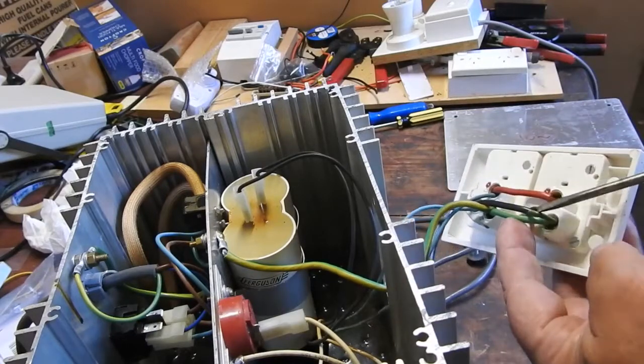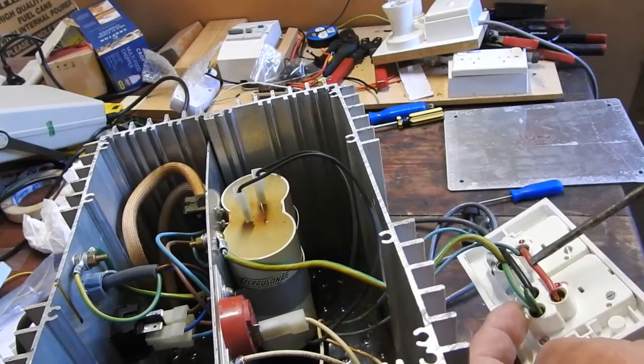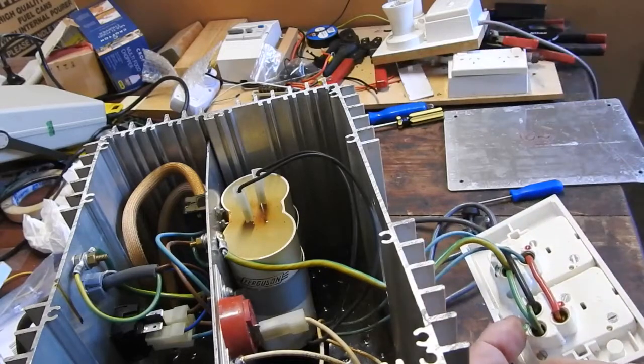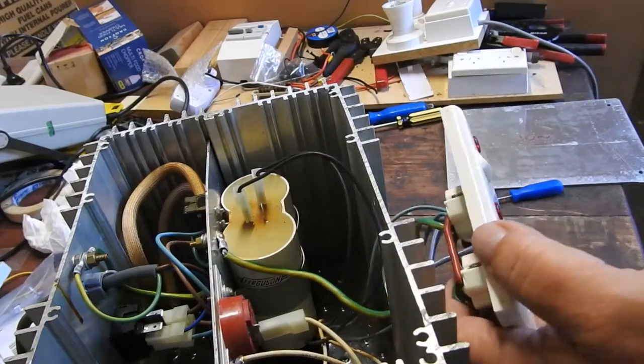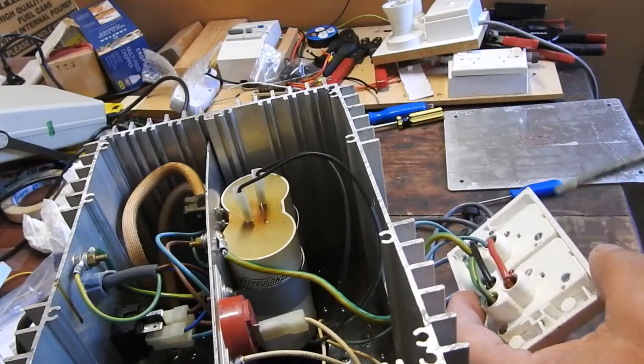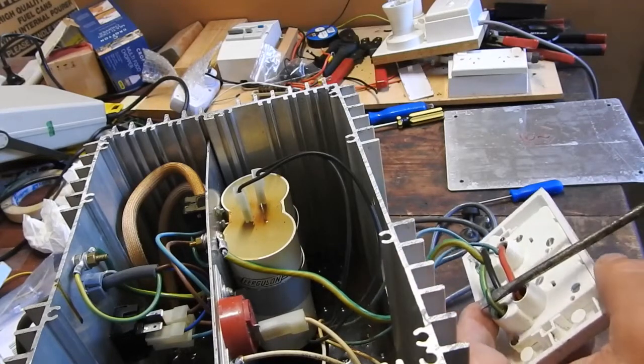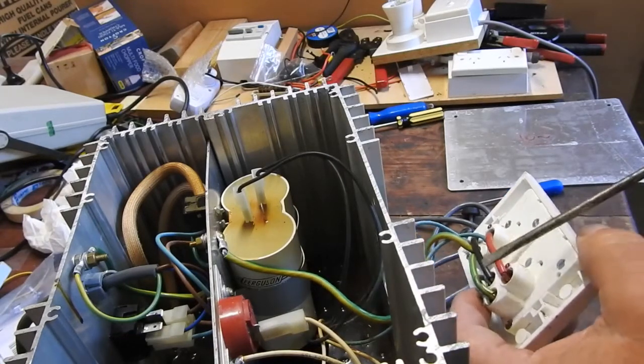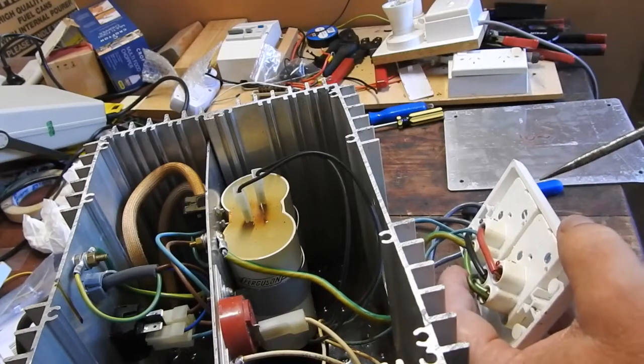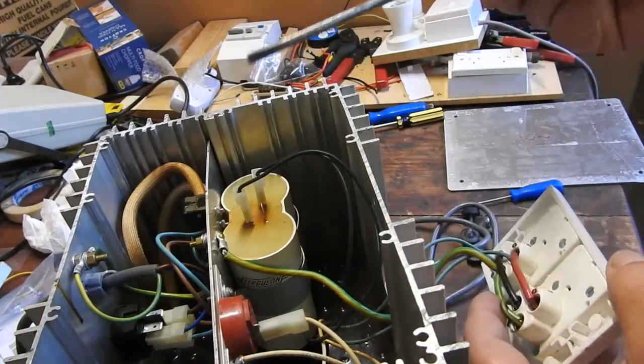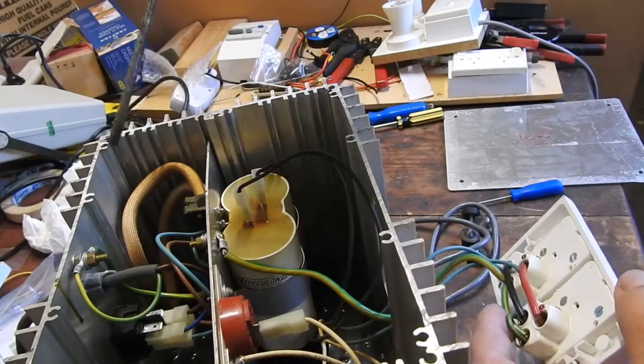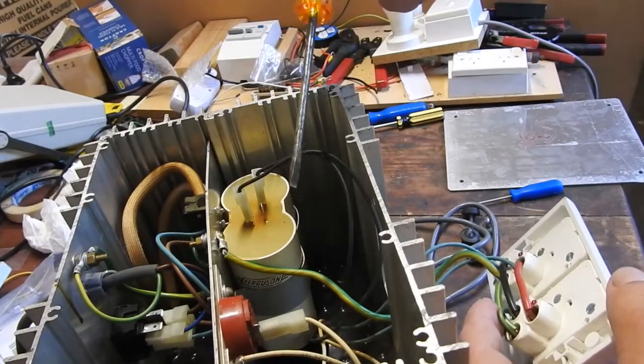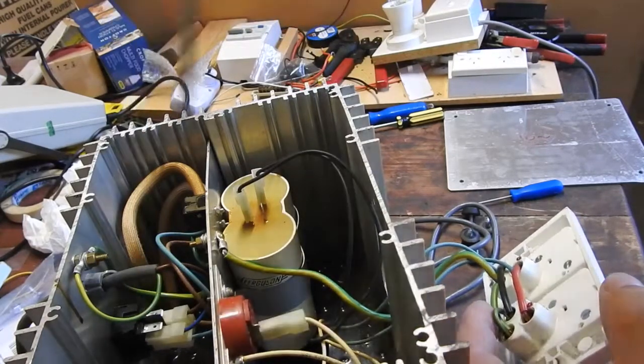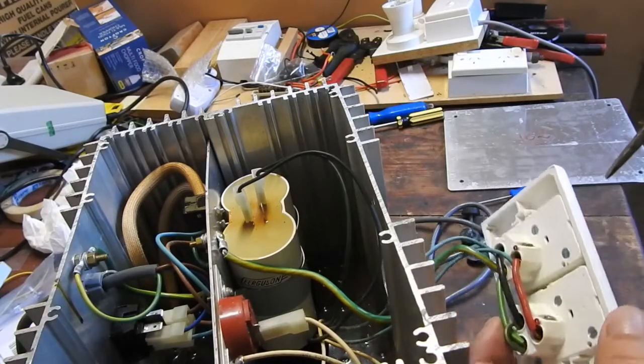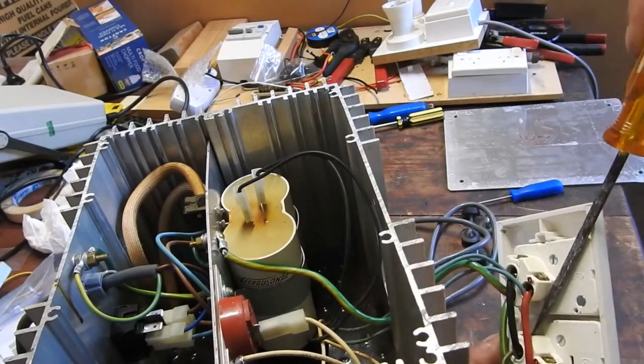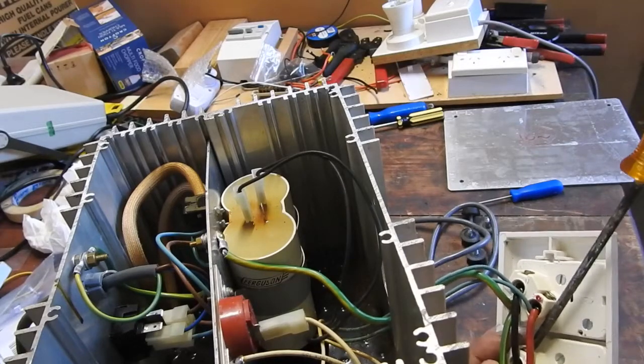So I might just disconnect that and see that the secondary is truly isolated from the primary. And then I wonder, what should I do? Should I leave that link out so that it is a true isolation transformer and it will be very well isolated, because being ferroresonant it will have the primary and secondary isolated physically, and then the potting on top of that gives further isolation.